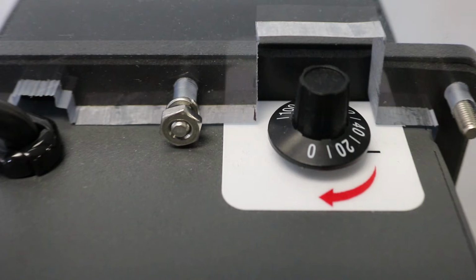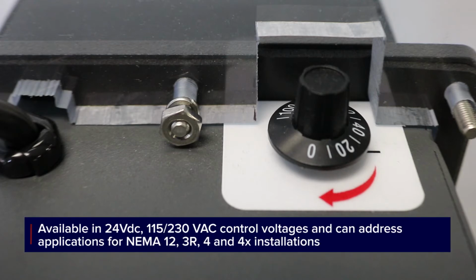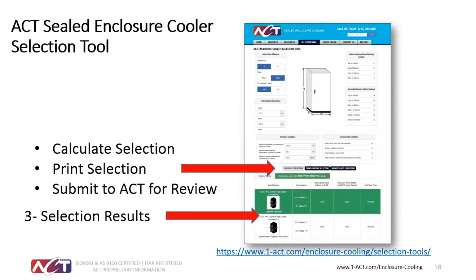The ACT TECs are available in 24 VDC, 115 to 230 VAC control voltages, and can address applications for NEMA 12, 3R, 4, and 4X installations. To make the application and selection process easy, ACT offers an online selection tool that provides a product selection based on your application parameters of panel size, mounting preference, operating temperatures, and heat loads. A simple click of the Calculate Selection tab provides choices closest to your application criteria.